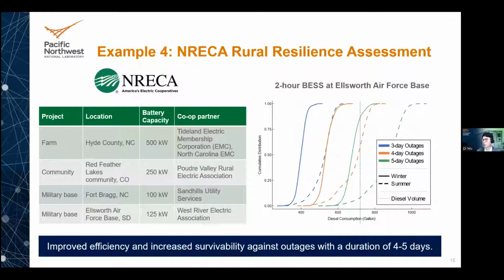The idea is to use battery energy storage to recover the fuel that would otherwise be wasted in a load bank when the building load is lower than the minimum loading level of the diesel genset, and use battery flexibility to improve fuel efficiency. The battery can also provide other services such as VAR support, power factor correction, and demand charge reduction.